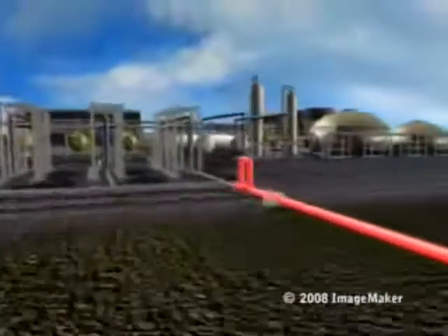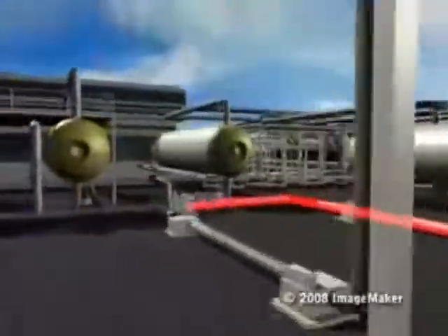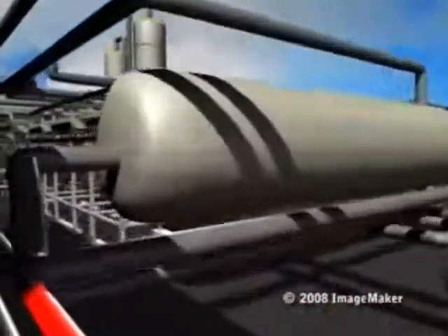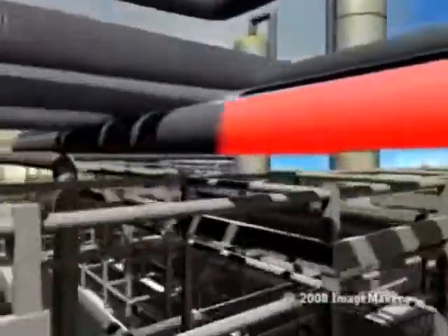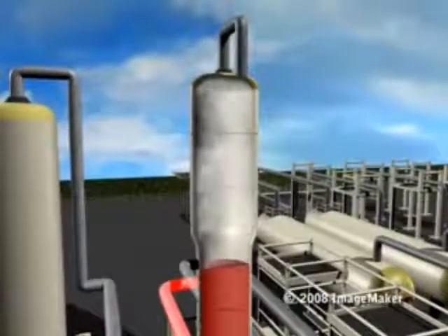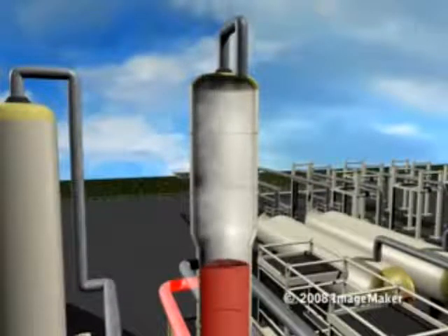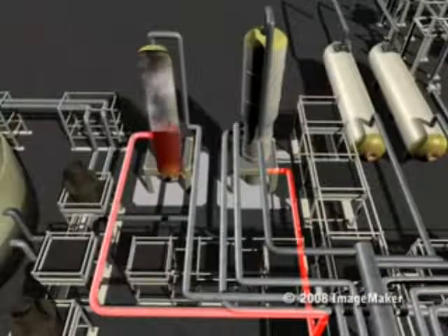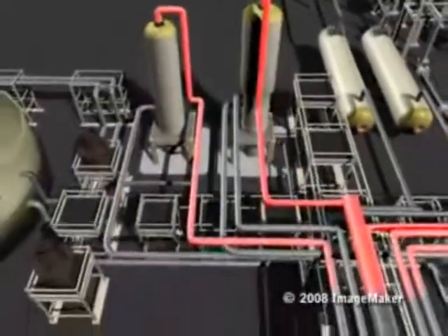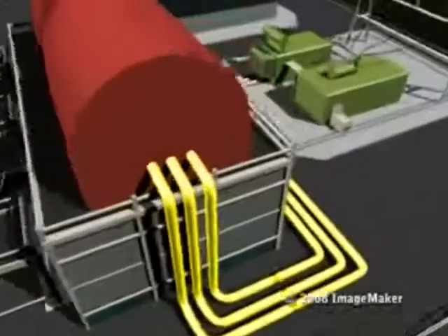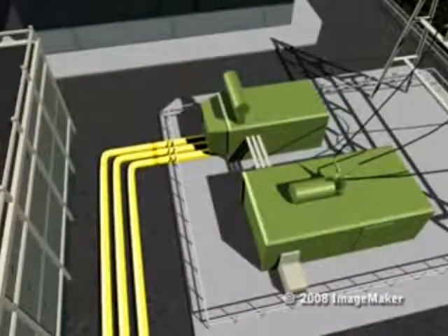As it goes up, the pressure lessens, causing some steam to form. Together, the hot fluid and steam move until they reach a separator where they flash into high pressure steam, and the hot fluid moves into another separator to flash into standard pressure steam. Extra hot fluids not in steam then move to another separator to flash into low pressure steam. All the steam created is sent to a shaft which turns a turbine to generate electricity. Any leftover fluids will return into the reservoir. It will eventually be reheated and reused.